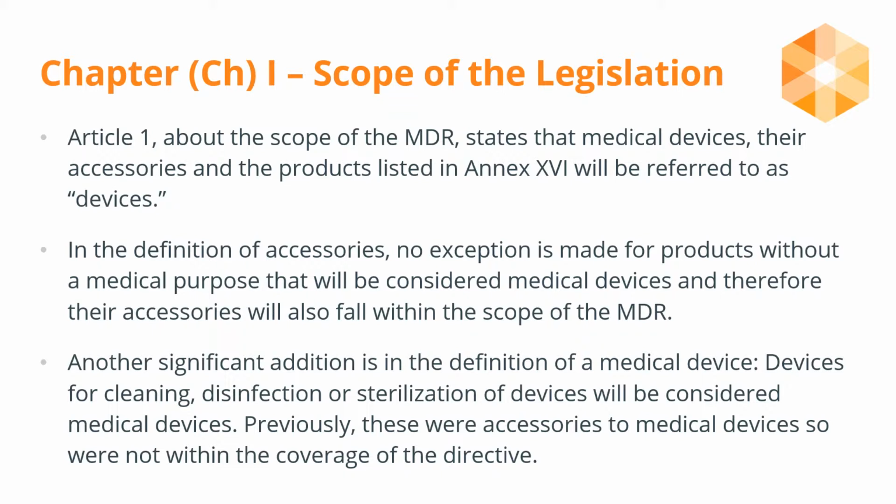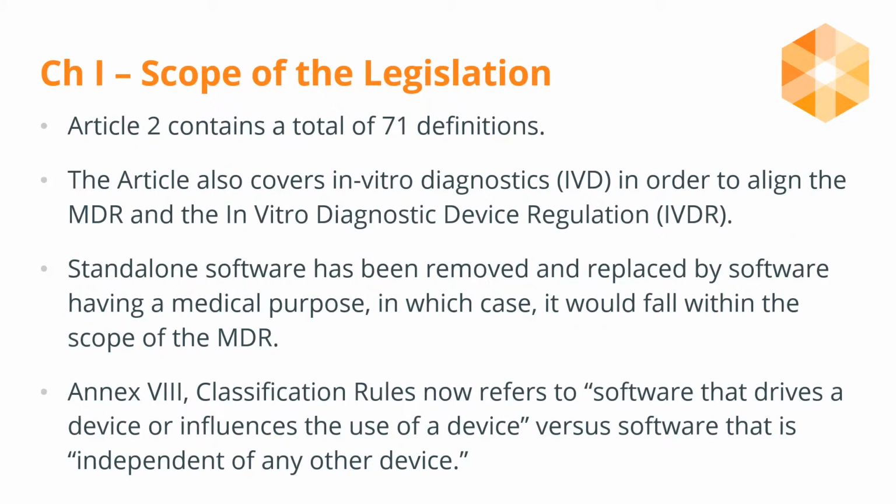Another significant addition was with the definition of a medical device. Devices for cleaning, disinfection, or sterilization of devices will be considered medical devices. Previously, these accessories to medical devices were not covered within the directive. The legislation also covers in vitro diagnostics in order to align the MDR and the in vitro diagnostic device regulation.